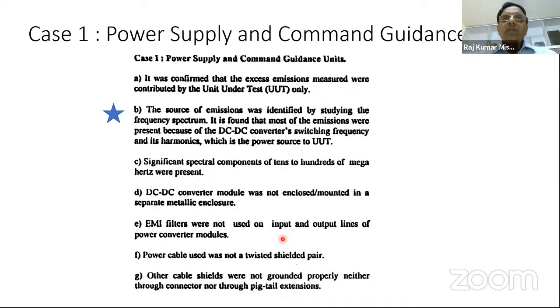This DC-DC converter module was not enclosed or mounted in a separate metallic enclosure, and EMI filters were not used on input and output lines of the power converter modules. Power cables used were not a twisted shielded pair. Other cable shields were not grounded properly, neither through connector nor through pigtail extensions.